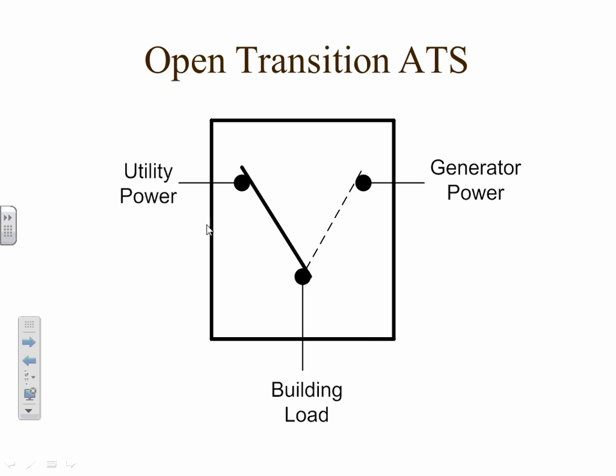Don't really need it. The third time delay, okay, we've been running on generator power now for several hours. Power comes back on. The transfer switch will see it in the voltage sensors over here on the utility side. So now what it's going to do is we have a time delay on retransfer. Why? Give you an instance. Instead of the cold, let's talk the heat in the summertime. Hot day in the summertime. Everybody has turned their air conditioning on.